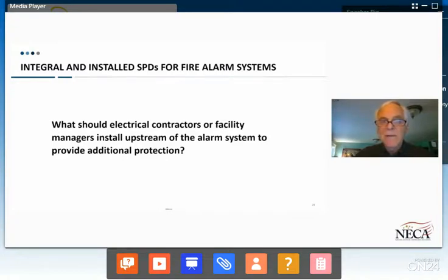We also pay close attention to proper grounding and bonding to comply with Article 250 of the NEC and to stabilize voltages. And most of that grounding and bonding is done by the electrical contractor at the building electrical distribution system level. And then we make sure that we bond and ground our equipment properly. However, we find that not all of our equipment that we install has provisions for terminating an equipment grounding conductor, as it is connected to the load side of a Class 2 transformer, which doesn't have a grounded conductor.